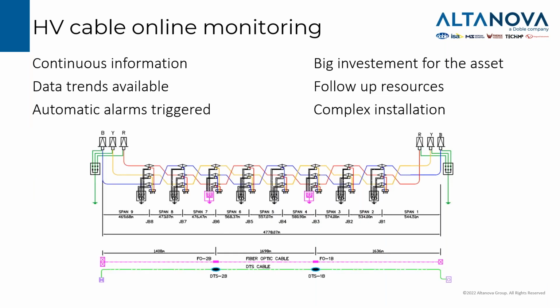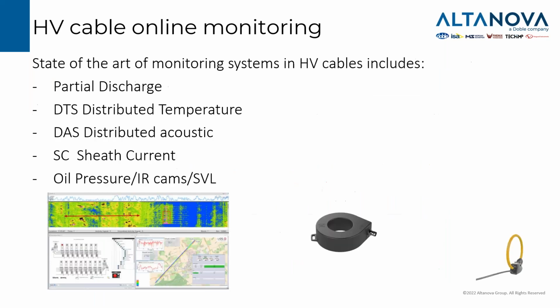When we move instead to high voltage cable monitoring, we can have a little bit more complex systems involved. Of course, the big advantage of permanent online monitoring is that we have continuous information flow, a lot of data trends, and automatic alarms triggered. On the other side, it's a huge investment. We need dedicated follow-up resources to analyze the alarms and take action with respect to the alarms triggered by the system. And the installation of the devices for the monitoring can be tricky and complex.